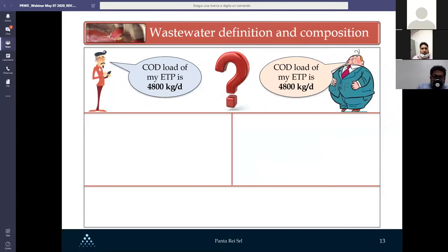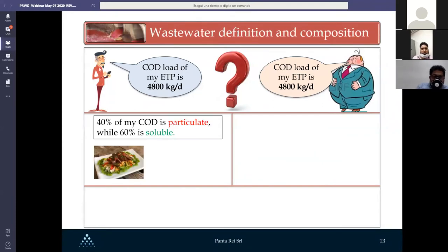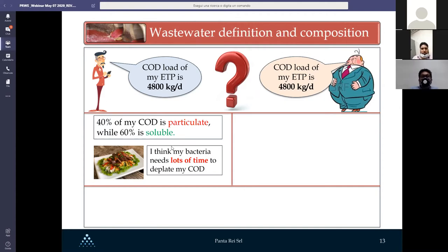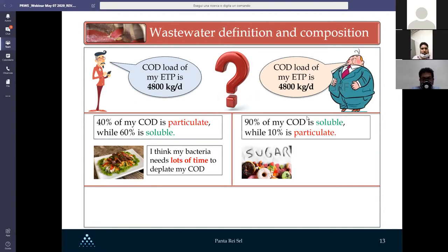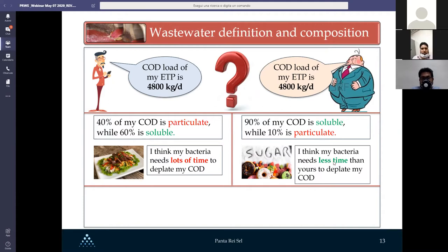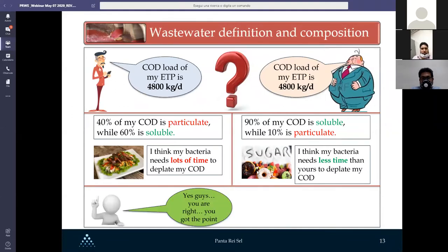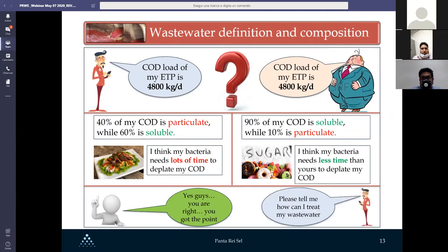In textile effluent, 40% of COD is particulate and 60% is soluble, so John's bacteria needs more time to deplete the COD. In a sweet and cake factory, 90% of COD is soluble and only 10% is particulate, so Frank's bacteria needs less time to deplete the COD. Understanding the characteristic and composition of your wastewater is essential to knowing how to treat it properly.